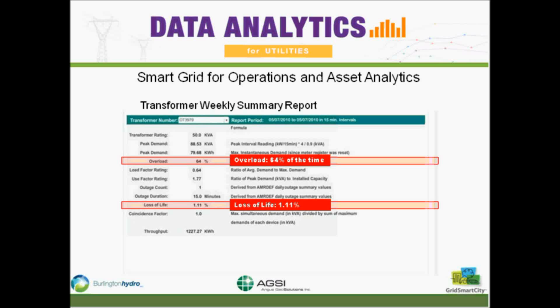It had one outage count for a total of 15 minutes. But what was interesting is it had a loss of life calculation factor of 1.11% for that day, which isn't good. It was one of the worst performing transformers in the territory, but obviously there's a problem.